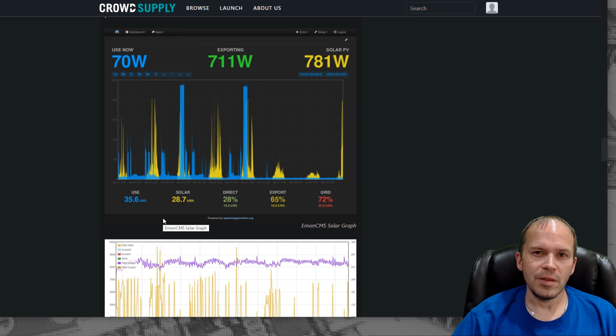One last bit on safety with the CT clamps: once you have a load on those clamps, do not unplug them from the board, especially the ones without an internal burden resistor — those with a milliamp output rather than a voltage output. Open Energy Monitor has some very great documentation and safety tips concerning all the CT clamps.